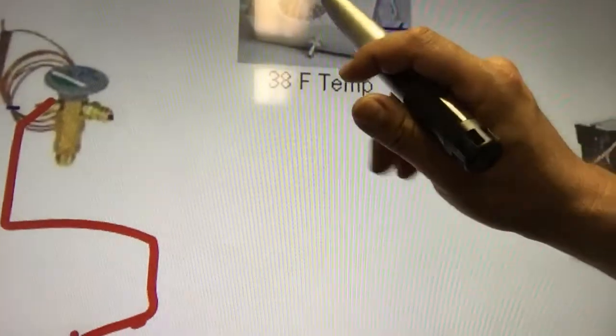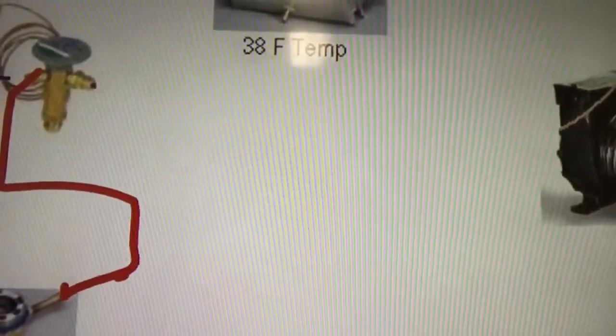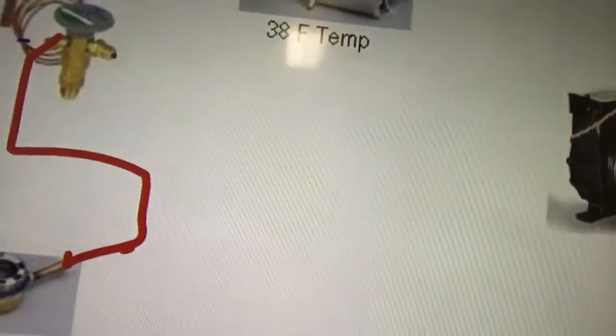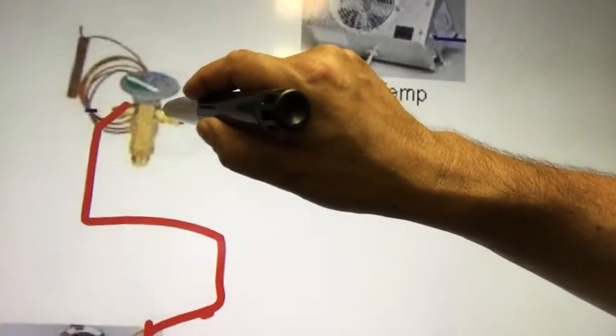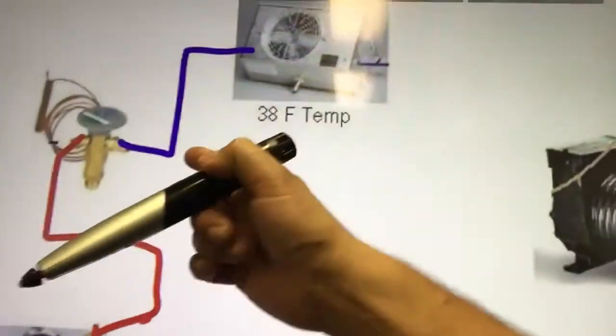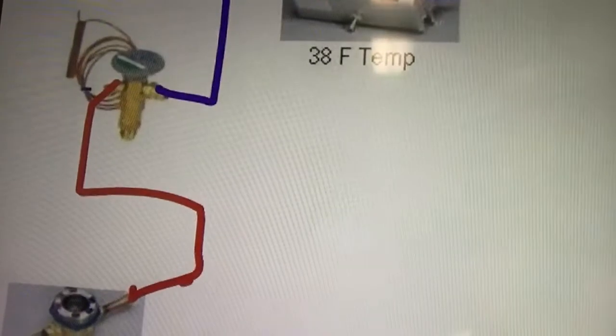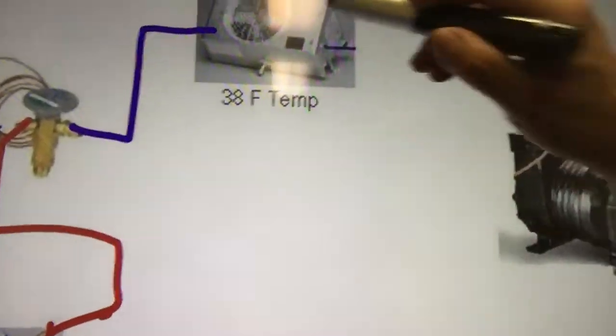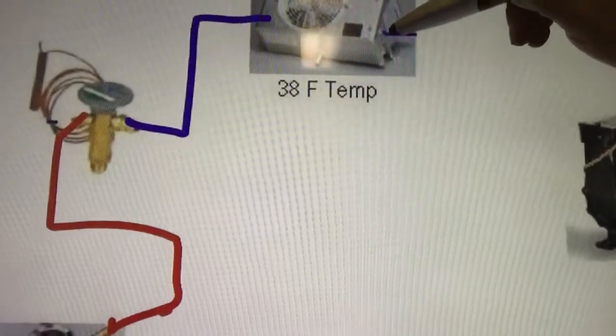From the TXV — the thermal expansion valve — there's a change. When the refrigerant passes through the TXV and goes into the evaporator, it becomes low pressure and mostly liquid: 90% liquid and 10% vapor, and this is where the refrigerant starts boiling. We change the color to dark blue from the TXV into the evaporator — dark blue represents 90% liquid, 10% vapor, boiling, low pressure.